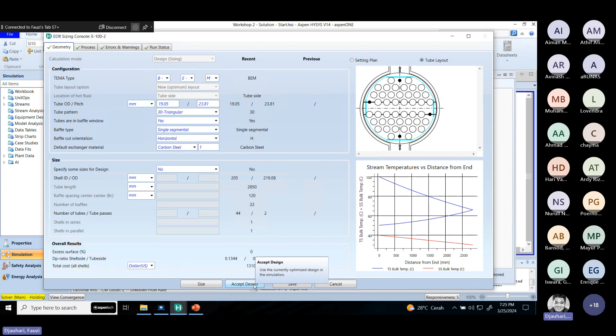When I click this accept design, it will transfer the geometry back to HYSYS. So if I click accept design, it will convert my simple heat exchanger to a rigorous shell and tube heat exchanger. So you can see here, this heat exchanger has become a rigorous heat exchanger. So how do I know? I double click here, I click here, is active.